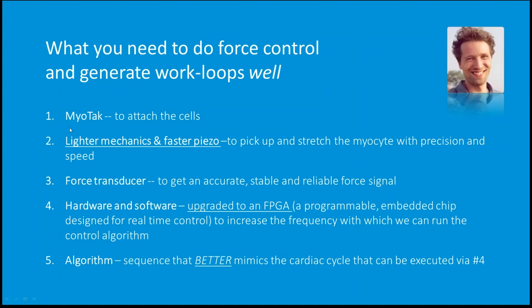This all doesn't change, but we had to get lighter mechanics so the piezo could move things faster. We decided to go to a direct drive piezo instead of the actuator they had, so there was no time lag in it starting to move, and it was just faster. Every millisecond counts in this case. The force transducer is still the same.